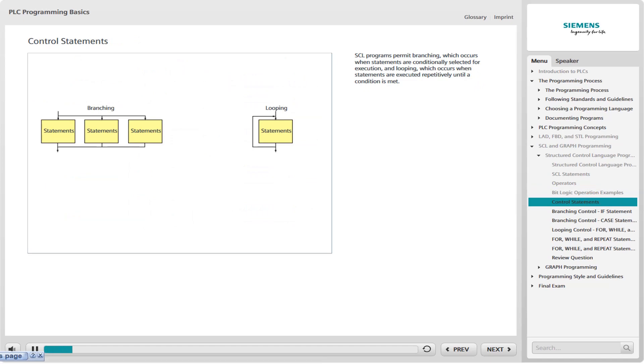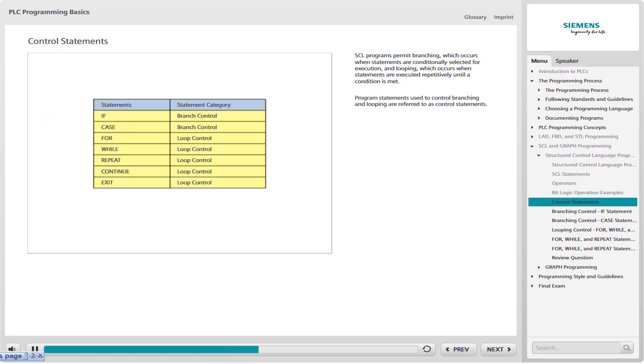SCL programs have statements that are executed in logical order, but not necessarily in consecutive order. This is because SCL programs permit branching, which occurs when statements are conditionally selected for execution, and looping, which occurs when statements are executed repetitively until a condition is met. Program statements used to control branching and looping are referred to as control statements. There are multiple types, and taken as a whole, these statements simplify programming and allow for more compact and readable program code.